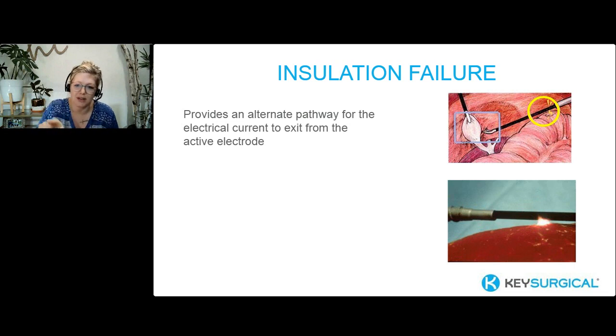So as we can see here, again, in that top picture, we can't see it. That blue box is our field of view. And outside of the field of view, we have a damaged instrument, damaged insulation, which we can't often see with just the naked eye, although we should be doing that evaluation as well. That's causing a burn here in this instance in the bowel, a place that we didn't intend. So kind of how this happens, we'll talk about in a few slides, but also the way that we think about this, we're going to talk about eschar in a second.